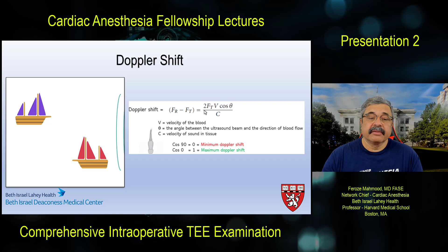So the first kind of Doppler is continuous wave Doppler, in which there are separate transmission and reception systems in a transducer. One crystal is continuously ringing and sending out the pulse, and the second one is continuously receiving all the reflected signals and establishing the highest Doppler shift, or the highest speed at which the target is moving. So there's one element to transmit and one element to receive, essentially having a duty factor of about 100%, or 1. Signals obtained from the region of overlap between the transmitted and the received signals have the highest sensitivity, and that's where you get the maximal Doppler shift. And that's continuous wave Doppler.